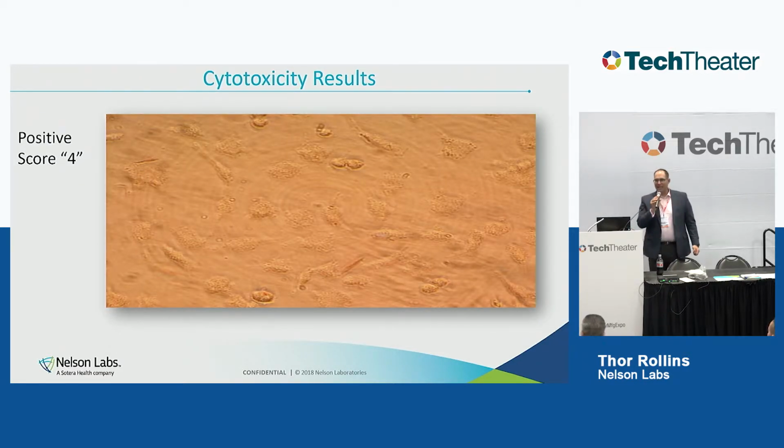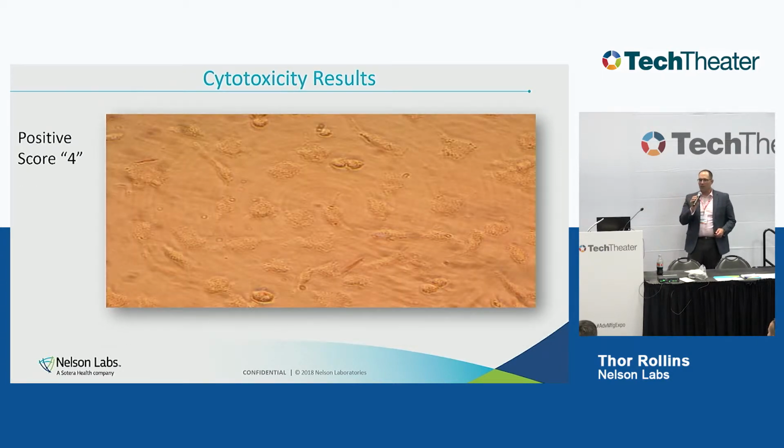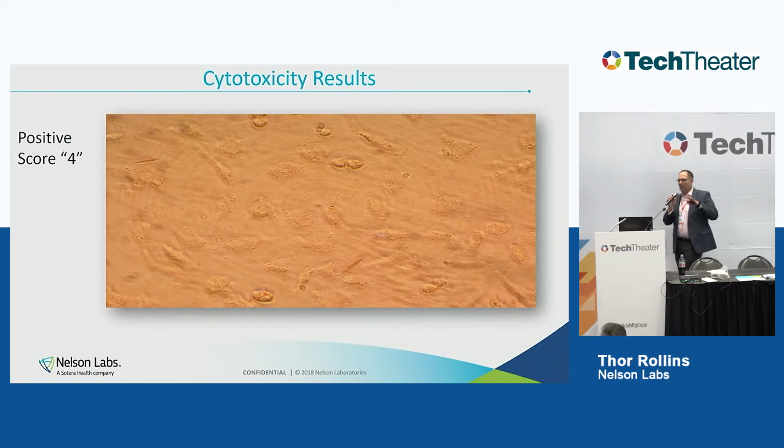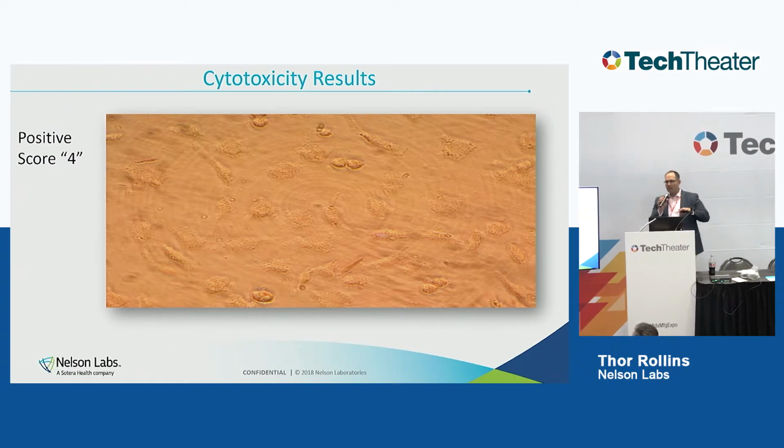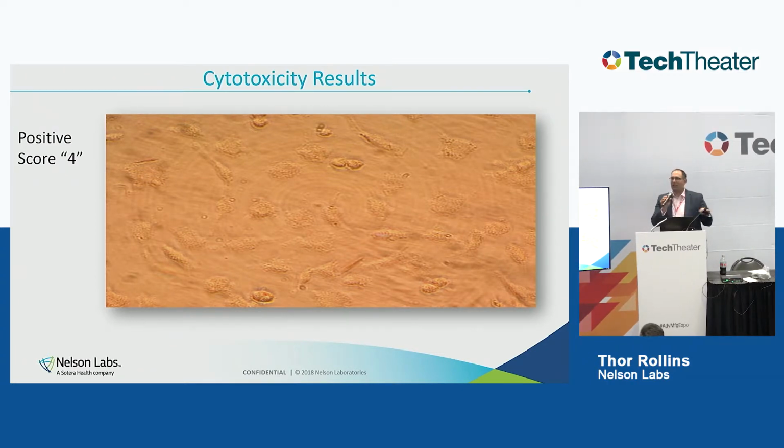This is actually latex. So latex is a fixative. It's really, really bad for cells. So please don't put latex in your devices, or else we'll have a discussion about failures, okay? So latex is my positive control. And as you can see, there's a pretty big difference, okay? The things on the bottom there that look like they may be cells is actually just the skeleton of the cell left behind. There's nothing there that's doing well, okay?